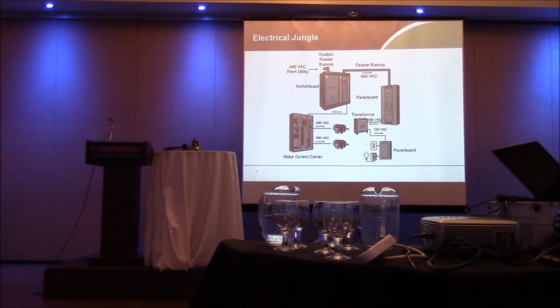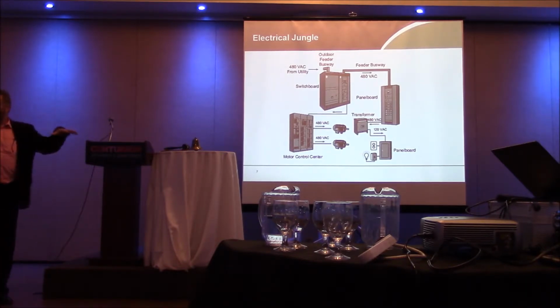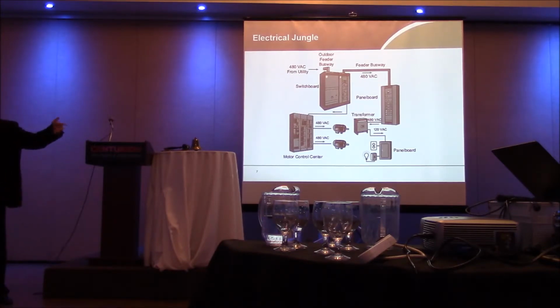Now, this slide makes reference to 480 volts AC because, frankly, I stole it from an American website. 480 volts is the standard voltage in the US for large distribution. In Canada, in most jurisdictions, we still use 600. And normally right about this point, somebody sticks their hand up and says, wait a minute, I see 575 on all my stuff. So 575 volts refers to a motor rating that says that motor, if receiving 575 volts, will still produce full rated horsepower. So when you give it 600 volts, it's more than happy. It's kind of like the lower threshold it'll work properly at. You go below 575 volts, if I don't tap the transformer correctly, then the motor doesn't have enough voltage to drive it, it'll overheat, you won't get the rated power out of it, the fan doesn't turn right.